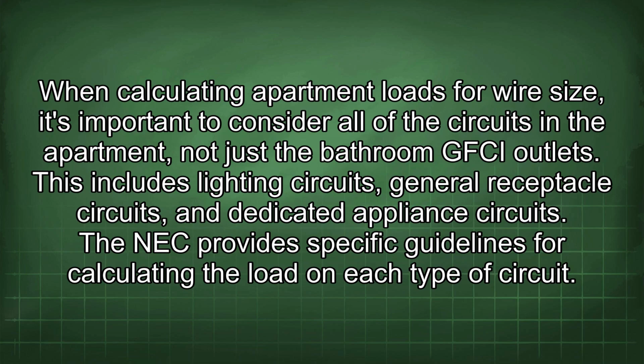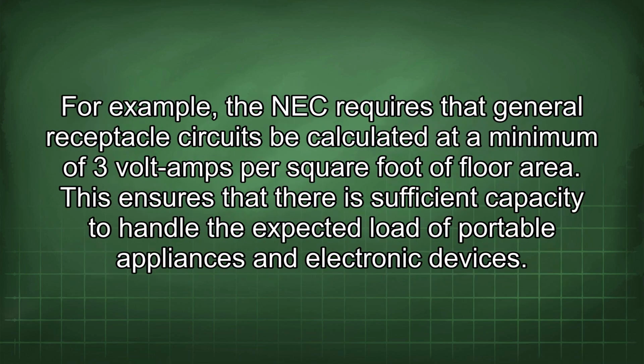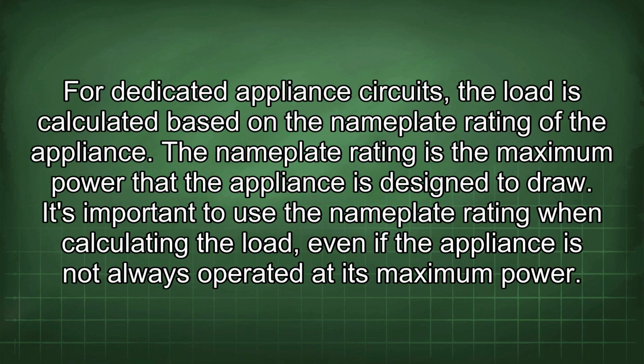When calculating apartment loads for wire size, it's important to consider all of the circuits in the apartment, not just the bathroom GFCI outlets. This includes lighting circuits, general receptacle circuits, and dedicated appliance circuits. The NEC provides specific guidelines for calculating the load on each type of circuit. For example, the NEC requires that general receptacle circuits be calculated at a minimum of 3 volt amps per square foot of floor area. This ensures that there is sufficient capacity to handle the expected load of portable appliances and electronic devices. For dedicated appliance circuits, the load is calculated based on the nameplate rating of the appliance. The nameplate rating is the maximum power that the appliance is designed to draw.